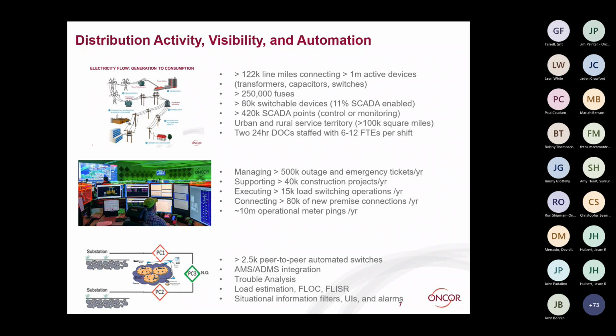What I want to add in that last section is, obviously, the distribution system for all of the distribution utilities is a system in transition. So we often still think about 80,000 switches, or 90% of them, still not being SCADA-enabled and manually operated on those radial lines. However, more and more technology and sophistication, data-driven things are coming online. As we deploy more SCADA-enabled switches on the distribution lines, several of those, in our case 2,500, are peer-to-peer automated switches, so they operate as a team. They're taking condition measurements on the line, and then they isolate an outage or a fault that occurs automatically, and reroute the power on those distribution lines through peer-to-peer communication without any interference or injection by the control room operator. So we have about 2,500 of them.